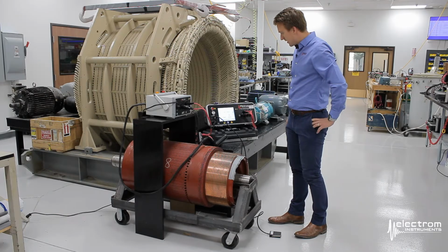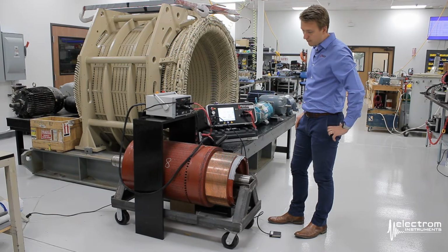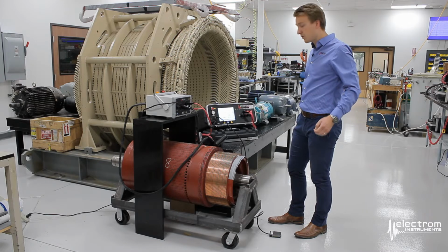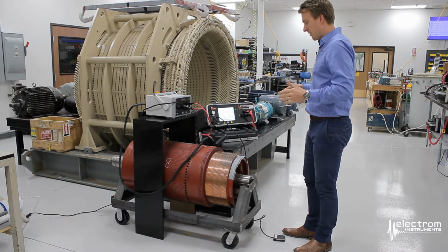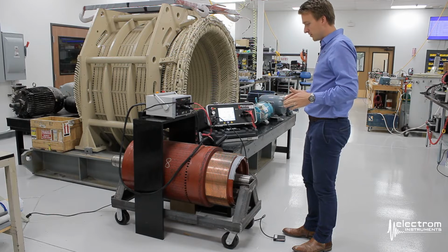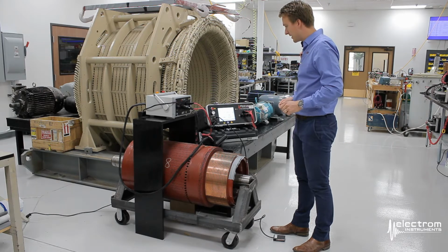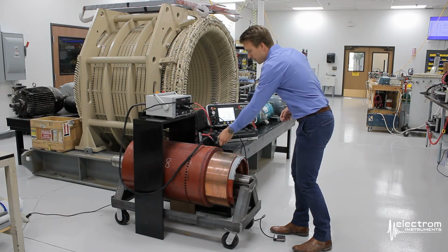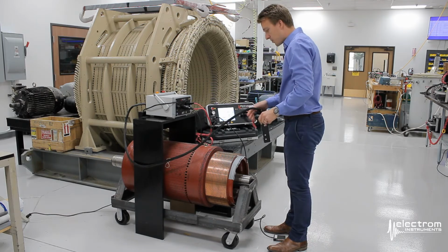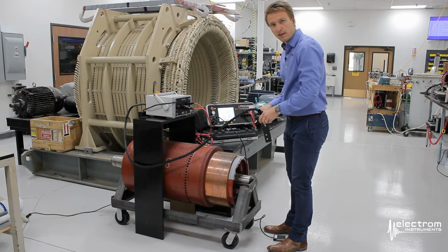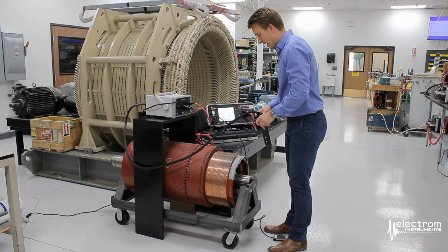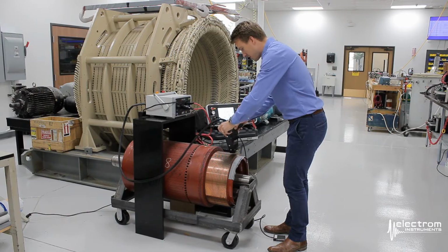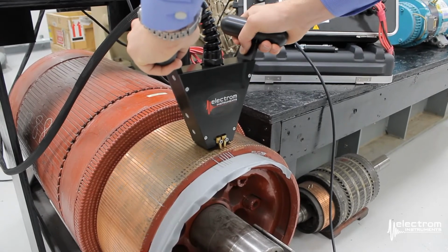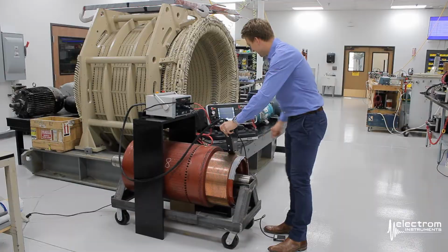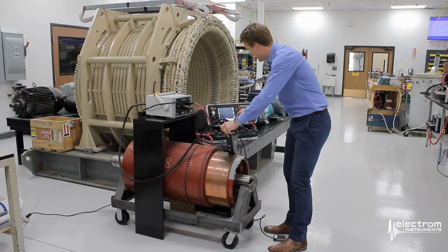Next step is to set your surge test voltage. In this case, we're going to use 750 volts. That's going to be the bar-to-bar voltage. Next, we want to make sure that we have a comfortable working position and that we have everything we need available. So you grab the probe sets. We will only do a few tests here so you can get an idea of what it looks like. But I know that I'll start about here. So now we can go to the surge screen and we arm the instrument.